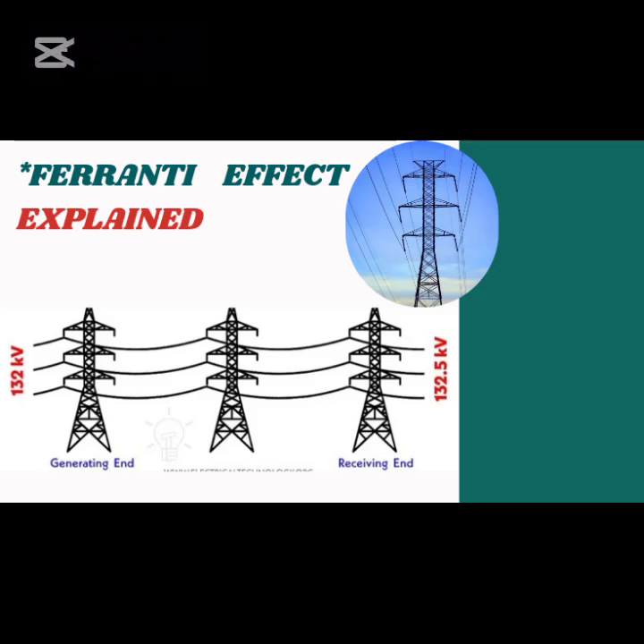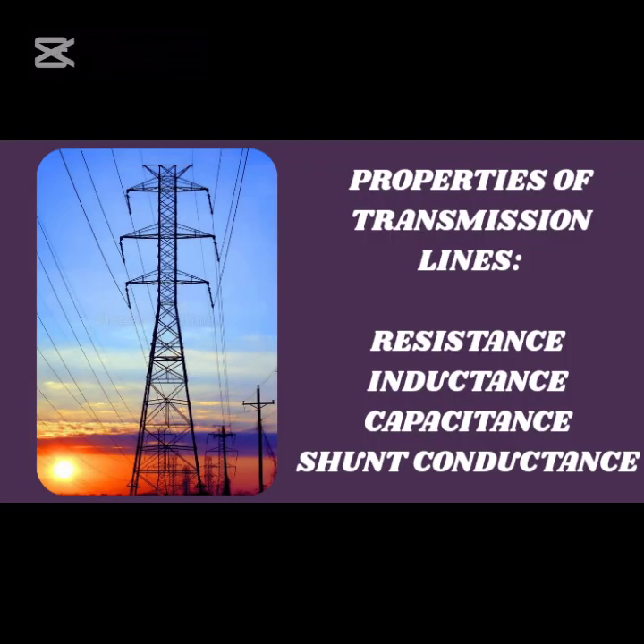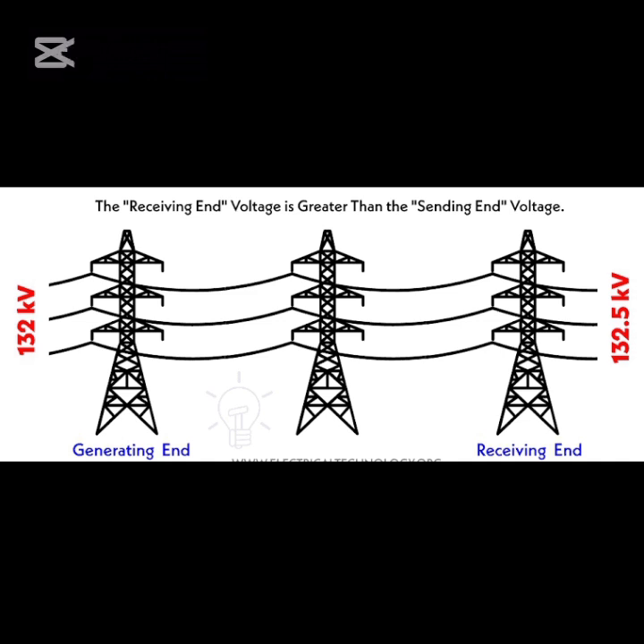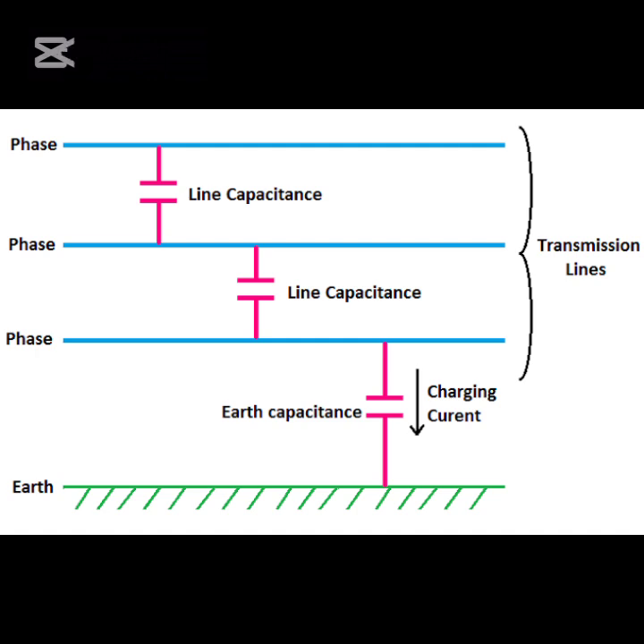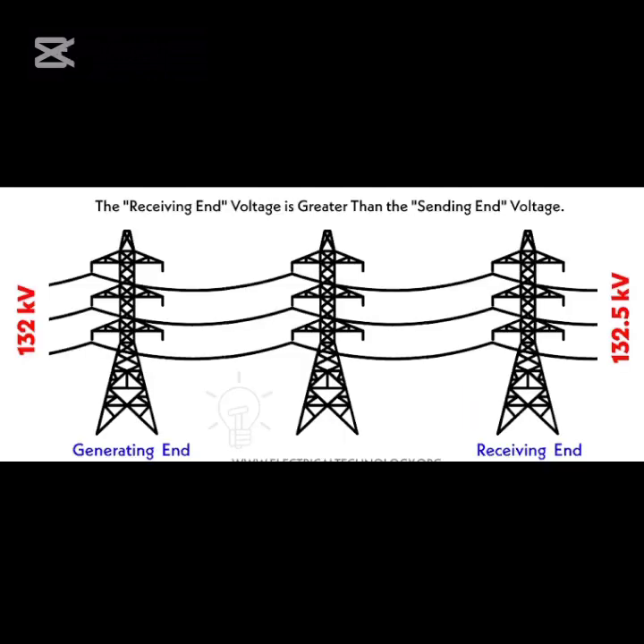Before diving into today's topic, I recommend you check my video on transmission line properties to gain a better understanding of capacitance, inductance, and their relation with today's topic — the link is in the description box below. The Ferranti effect is a phenomenon in which the voltage at the receiving end is greater than the sending end voltage of a transmission line during light load or no load conditions. The rise in voltage is due to more reactive power being generated by the line capacitance than the power being consumed by loads. Note that the Ferranti effect doesn't occur in short transmission lines; it only occurs in medium and long lines.